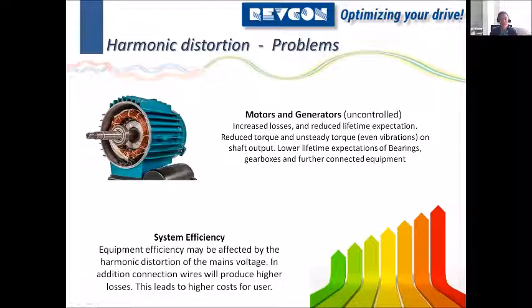Yes, motors and generators direct online, uncontrolled, always have increased losses, which will reduce lifetime expectation. They can have reduced torque and unsteady torque. And I think that's one of the main underestimated problems of harmonics looking at motors, because any motor direct online will try to follow the frequency of 50 or 60 hertz, depending on how many pole pairs you have connected. But anyway, they will try to follow the frequency. So if on the same voltage we add a frequency of 250 hertz, the motor will try to follow this frequency, and it can to a certain level. So it doesn't mean that it will not see this voltage. It can see the voltage, and it will cause a magnetic field, and this magnetic field will cause vibrations on the shaft, and these vibrations will damage the bearings very soon.